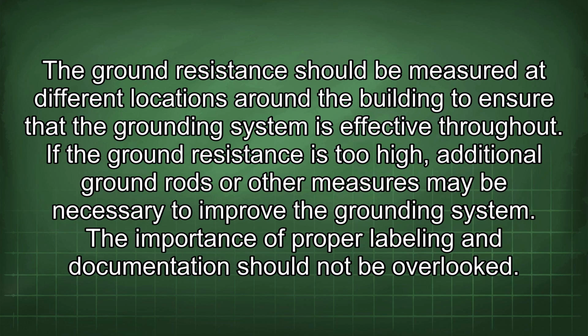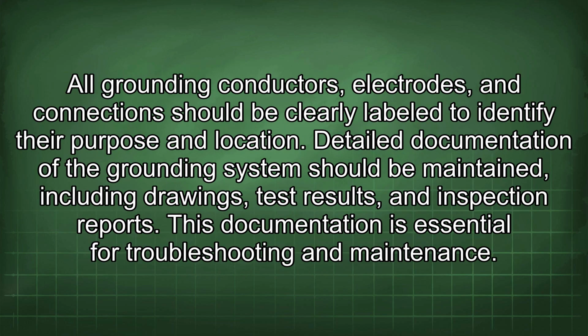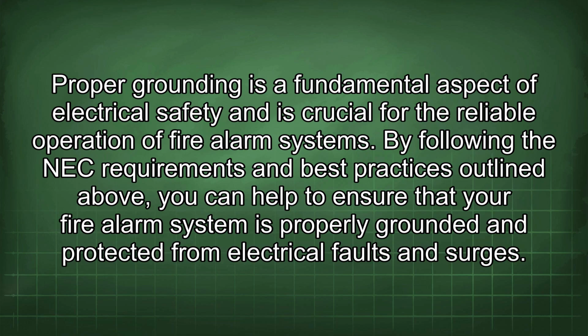The importance of proper labeling and documentation should not be overlooked. All grounding conductors, electrodes, and connections should be clearly labeled to identify their purpose and location. Detailed documentation of the grounding system should be maintained, including drawings, test results, and inspection reports. This documentation is essential for troubleshooting and maintenance. Proper grounding is a fundamental aspect of electrical safety and is crucial for the reliable operation of fire alarm systems. By following the NEC requirements and best practices outlined above, you can help to ensure that your fire alarm system is properly grounded and protected from electrical faults and surges.